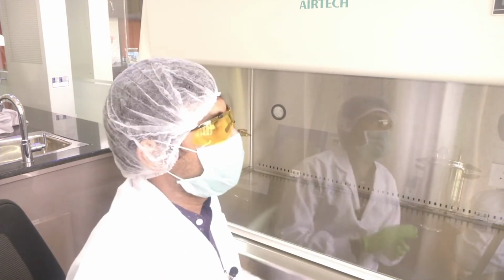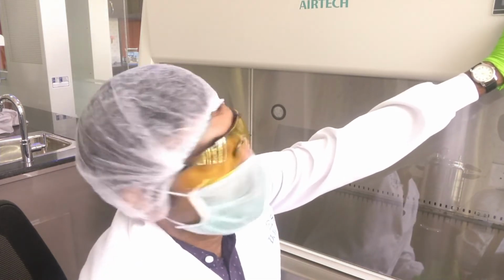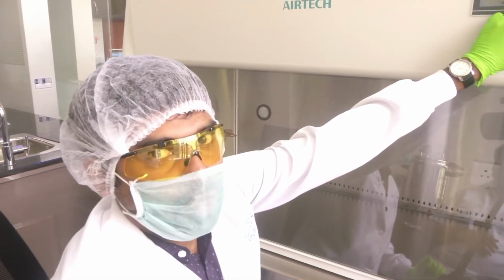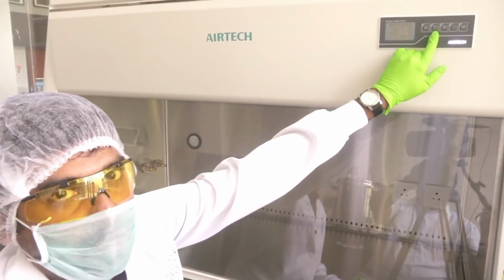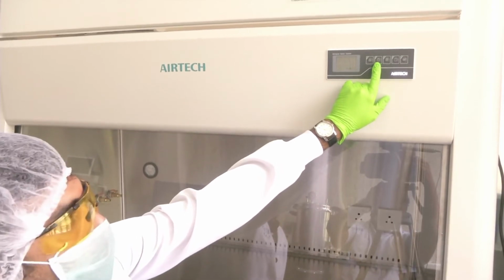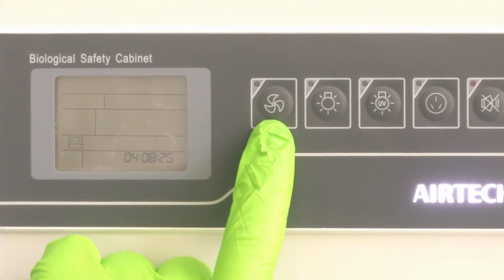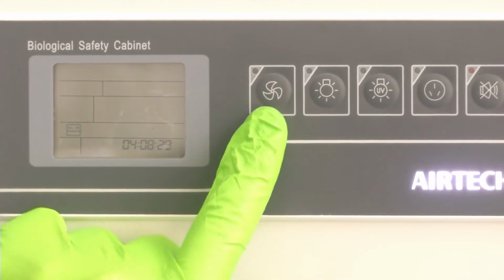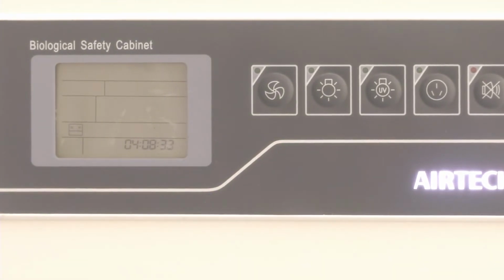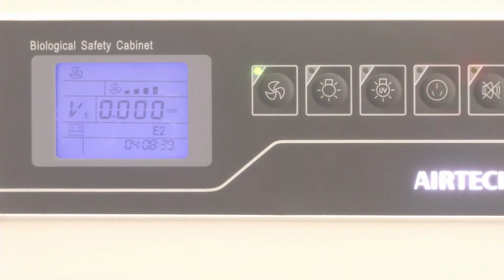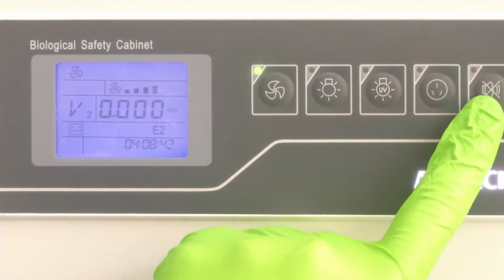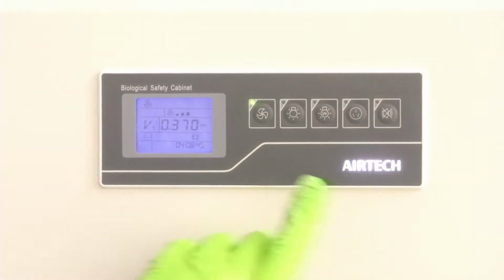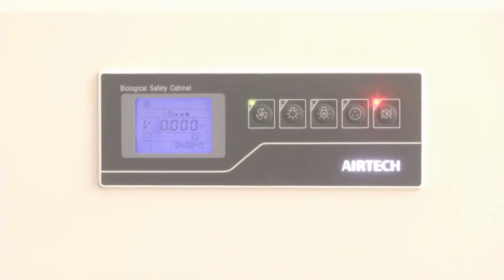Now we understood about the UV light, right? The second option that is provided is for normal visible light. We will shortly see the normal visible light, and then the first knob is for circulation, fan and exhaust. So before we start using the biosafety cabinet, the protocol is that we should always have the UV light on. The UV light is on. This fan should be running. When you switch on the fan, the alarm will ring here. The alarm is ringing because it needs some time to reach that circulation speed. It is telling me that I have not reached my set speed, so please wait.